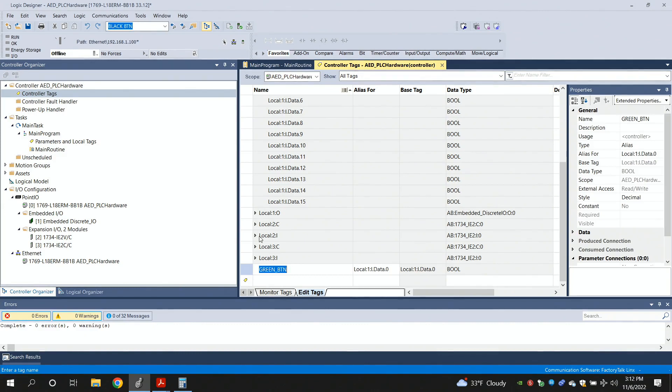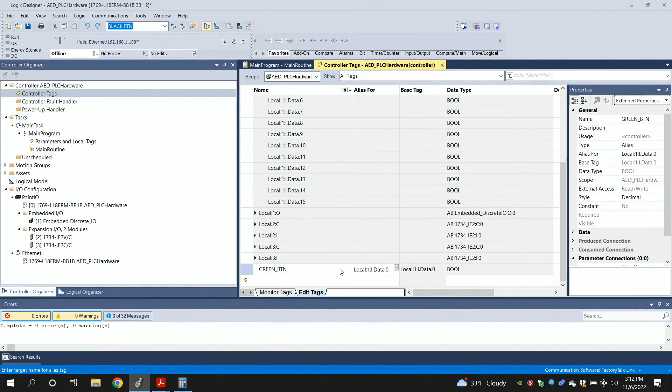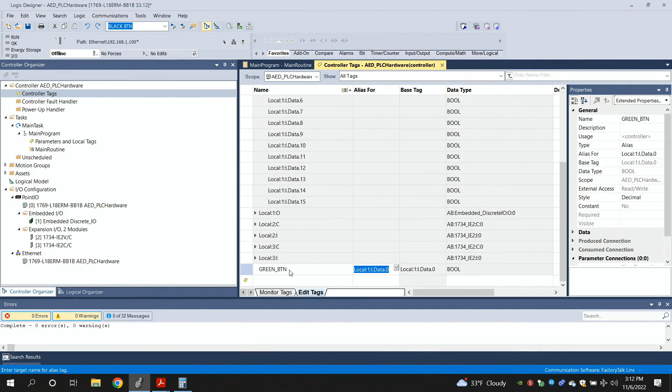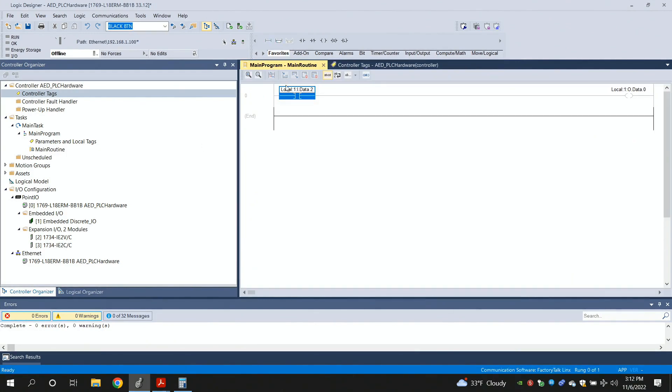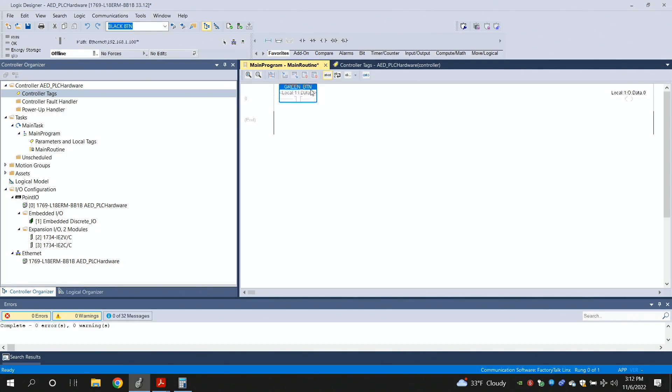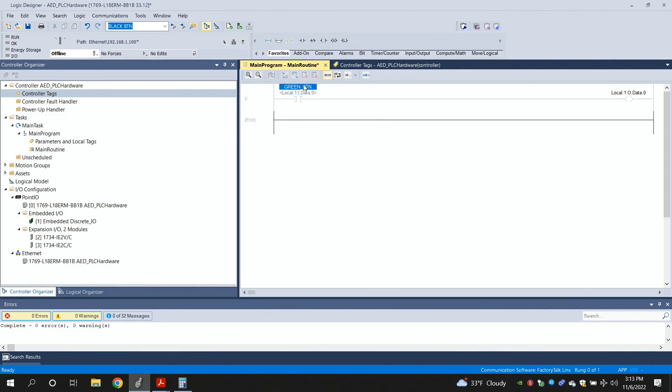Creating a tag that means something, it basically says that's an alias for this. So, instead of typing this out in my program, I can substitute green button, which means something more to me. Instead of having it called out like this, which, I don't know, that's just the input number that's there, I can just type in green push button and it pops up as an alias for that. And it should behave the same way as it did before.